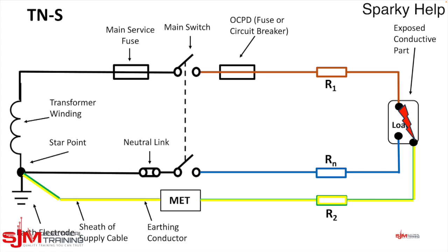Well now we introduce the fault. Here's a fault. Not that we want one but when we do we want a big fault. A fault of negligible impedance. And we're going to label it as such. And therefore current will flow in this path. And there we have it. This is the earth fault loop path for a TNS system.